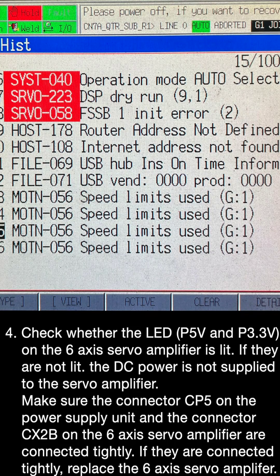Step 4: Check whether the LEDs P5V and P3.3V on the 6-axis servo amplifier are lit. If they are not lit, DC power is not being supplied to the servo amplifier. Make sure connector CP5 on the power supply unit and connector CX2B on the 6-axis servo amplifier are connected tightly. If they are connected tightly, replace the 6-axis servo amplifier.